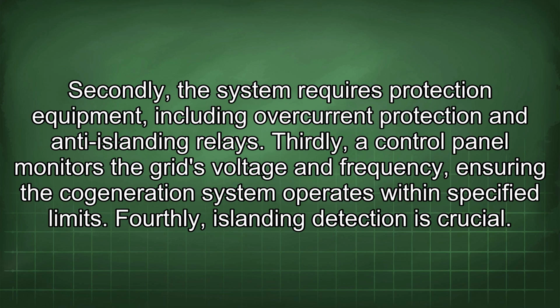Secondly, the system requires protection equipment, including overcurrent protection and anti-islanding relays. Thirdly, a control panel monitors the grid's voltage and frequency, ensuring the cogeneration system operates within specified limits. Fourthly, islanding detection is crucial.